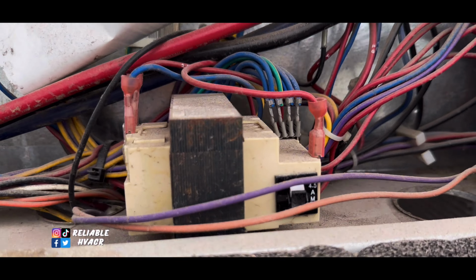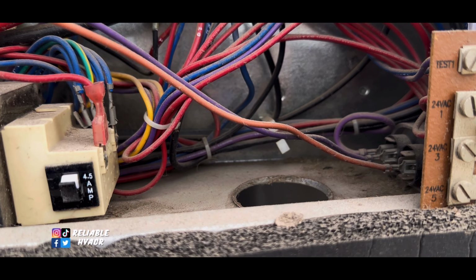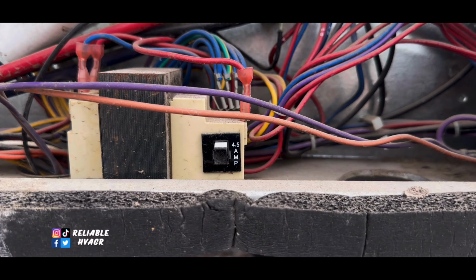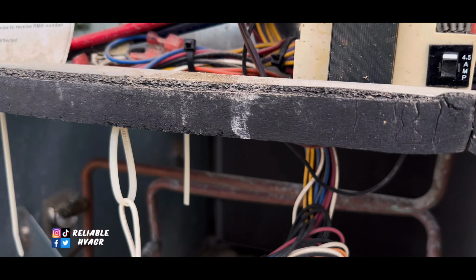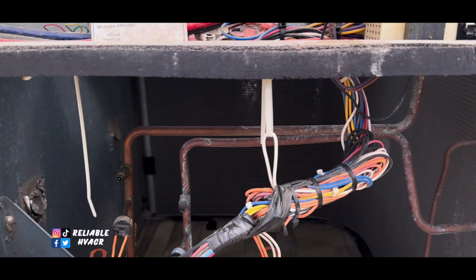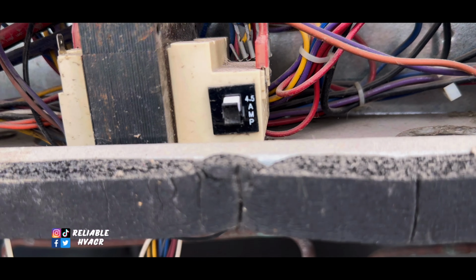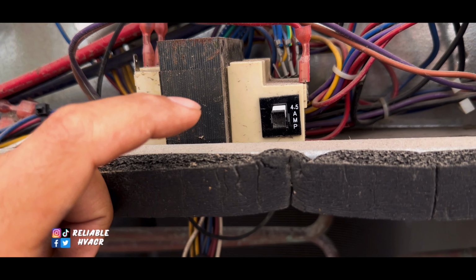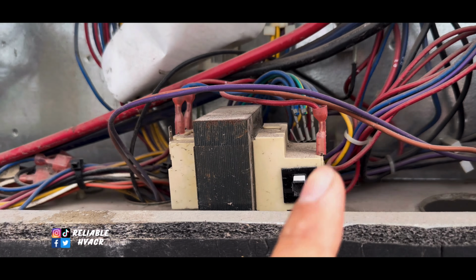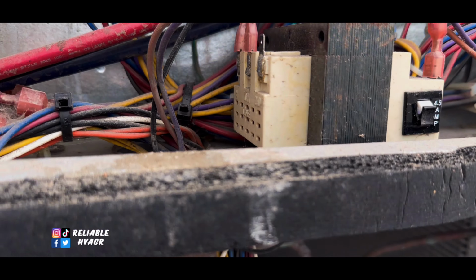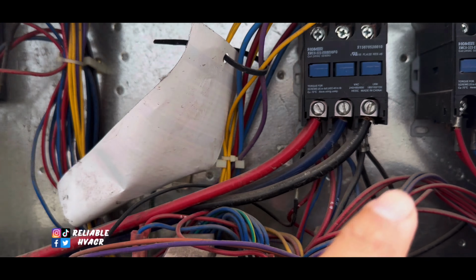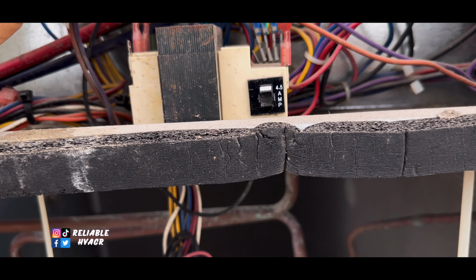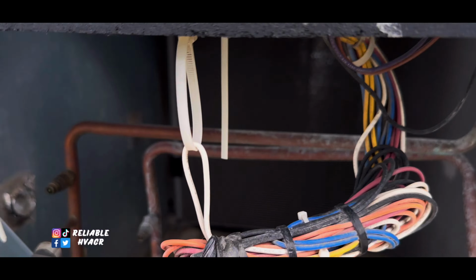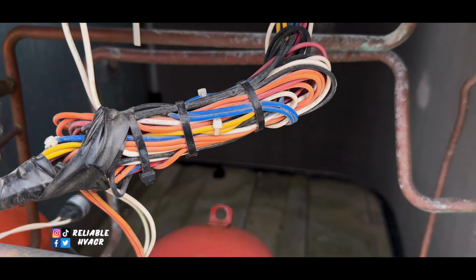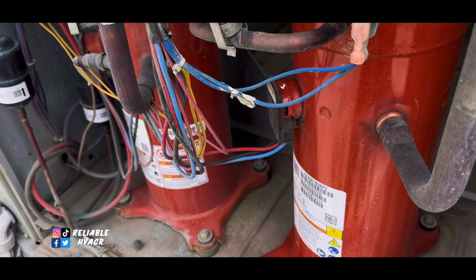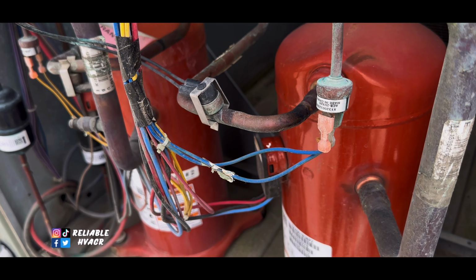All right, we got a popped transformer. So we're going to do the usual. We're going to disconnect power. The disconnect looks shot too. And then go through and make sure if there's a short. So it's going to be some sort of low voltage short, so I've got to make sure there's no rub-outs. This one is fairly new, but did not age well.